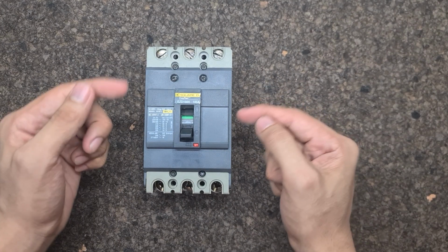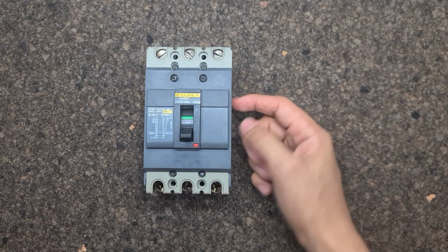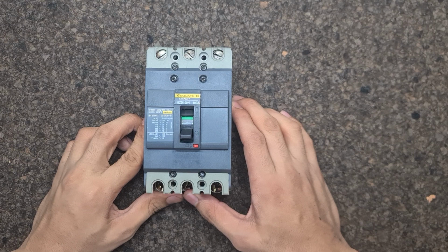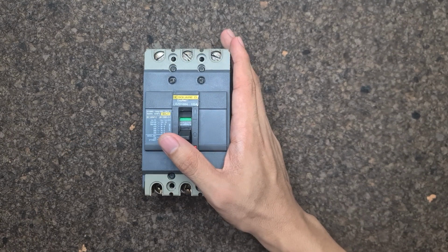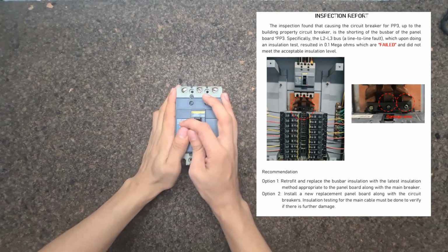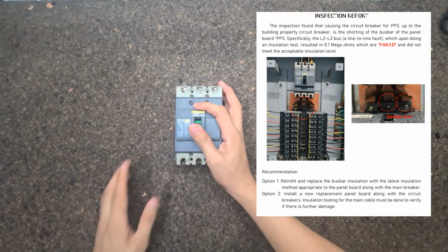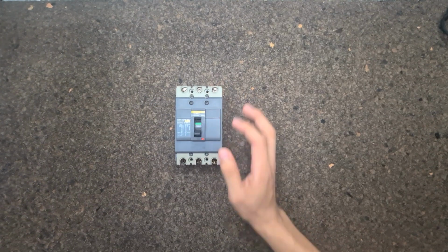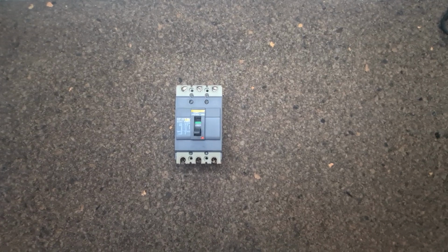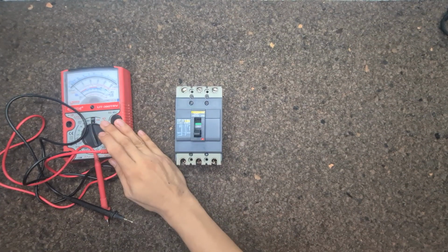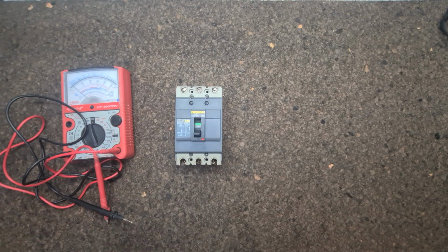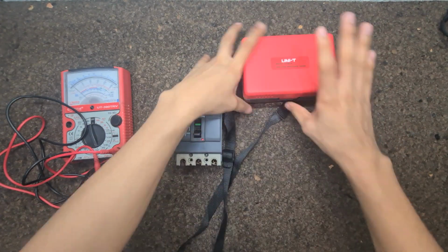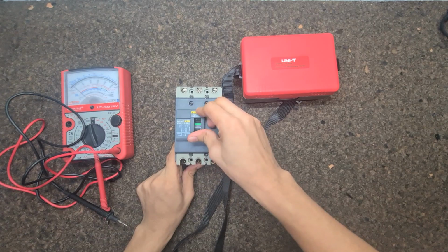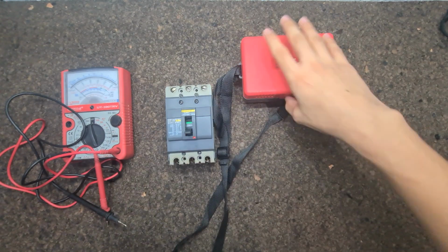Quick background, this breaker is a main protection for lightings and receptacle outlets only, then faults happened. Here's the inspection report I submitted to the owner for this occurrence. Let's try to do a simple testing before opening the breaker. I have here a multi-tester just to test the continuity of the breaker, and an insulation tester for finding out the insulation level between phases.